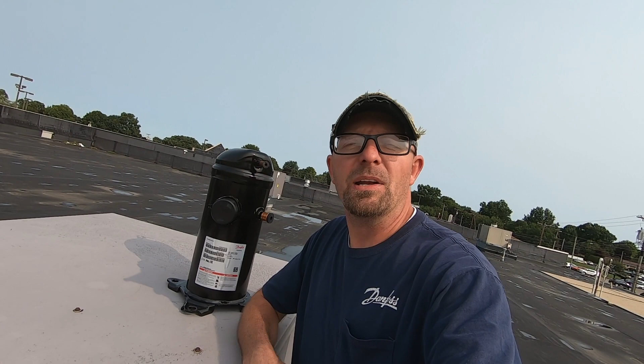Today we're gonna be replacing a compressor. I was out a few weeks back doing a leak search on this Carrier rooftop unit, found the leak on the compressor itself. When I pulled the compressor, I'll show you where it was leaking. Hope everybody out there is working, staying busy, staying safe. I'm gonna go ahead and pull this compressor out. It's flat, there's no refrigerant to recover, so we're gonna get right to it.